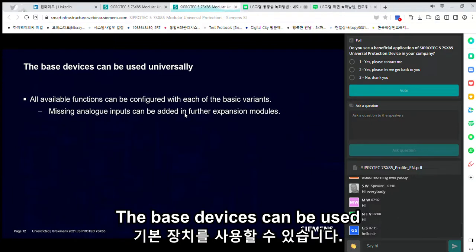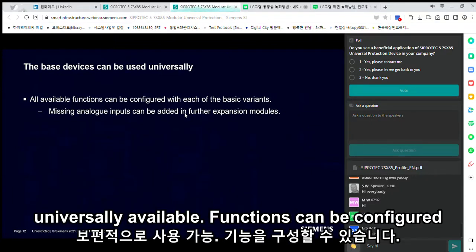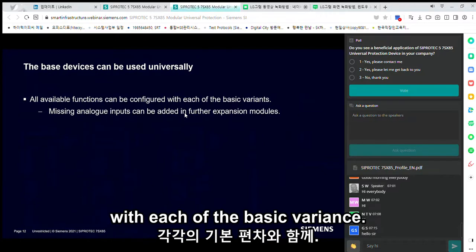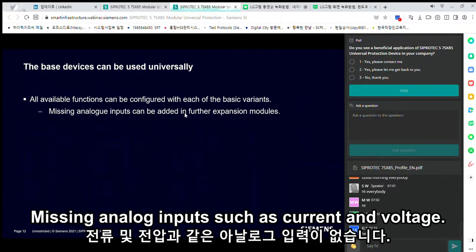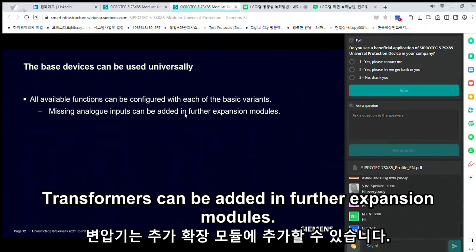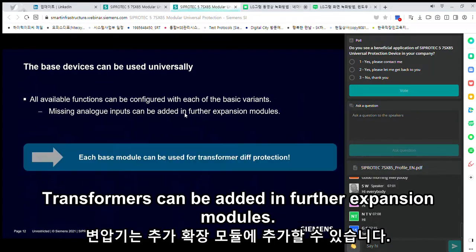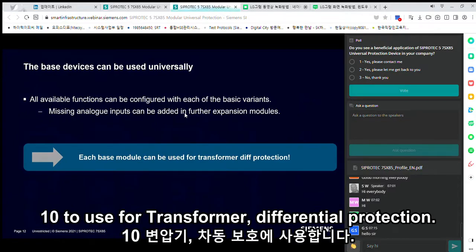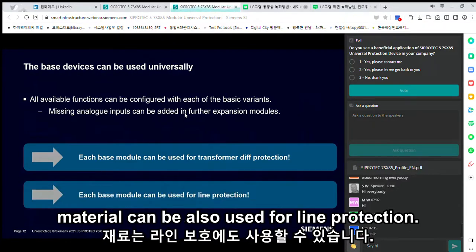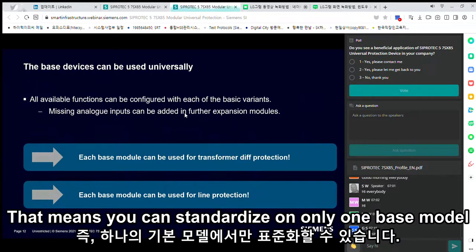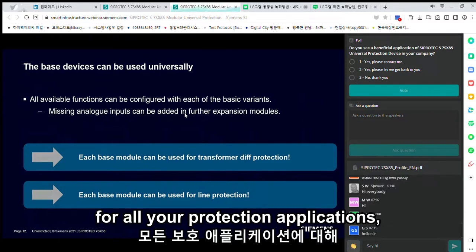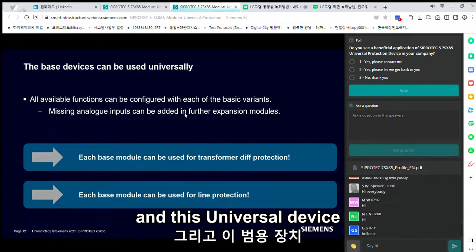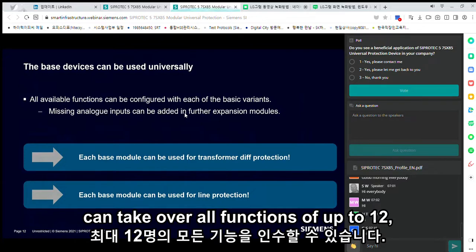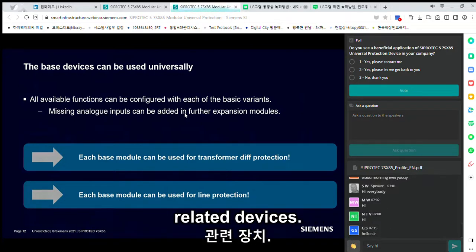The base devices can be used universally. All available functions can be configured with each of the basic variants. Missing analog inputs, such as current and voltage transformers, can be added in further expansion modules. So each base module can be used for transformer differential protection, and each base module can also be used for line protection. That means you can standardize on only one base module for all your protection applications. And this universal device can take over all functions of up to 12 individual type-related devices.